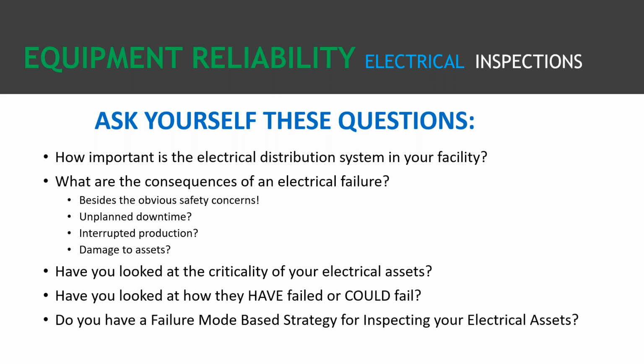Lastly, do you have a failure mode based strategy? Look at the different assets, how they potentially could fail, and whether you have a technology that matches up with that failure mode. When we look at ultrasound, any ionization-based failure mode is something you should address with ultrasound. Any resistance-based failure mode is better addressed with infrared. Not every technology identifies every failure mode, so when putting your program together or adjusting it, look at a failure mode based strategy based on your knowledge of those assets and how they could potentially fail.